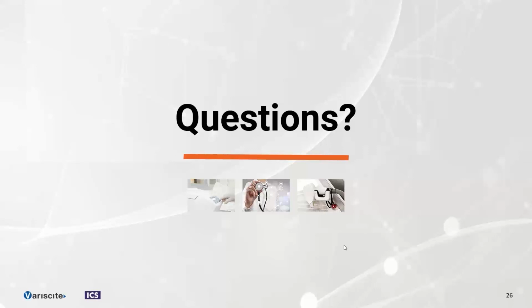That's another good question. Really, as I mentioned earlier, Android and Linux will really be part of the SOUP, software of unknown provenance. So as long as you can list the SOUP and you can do some testing to know that it fulfills your requirements, it should be good to use. Now, if you ask me for a medical device, I will no doubt use Yocto instead of Android, because Android is more targeted at massive consumer use, and you can really get very good interfaces, as good as Android, and even better with Yocto than with Android. Normally people use Android because sometimes they find developers more easily, sometimes because they are used to the way they are being developed. But you can really have amazing interfaces using Yocto too.